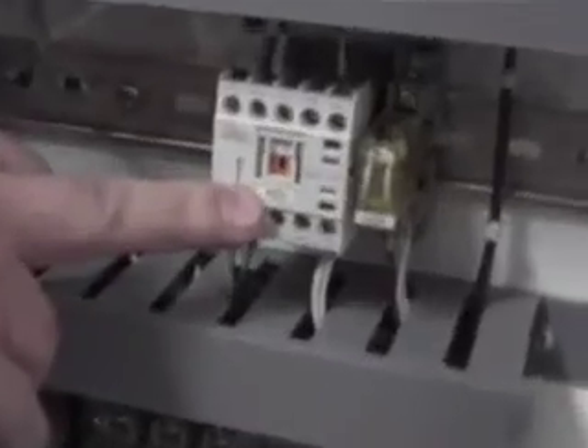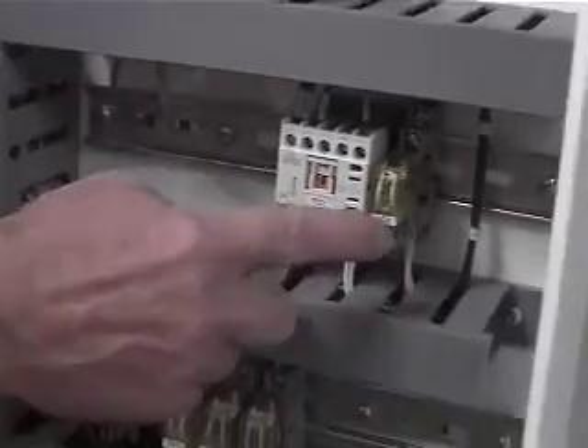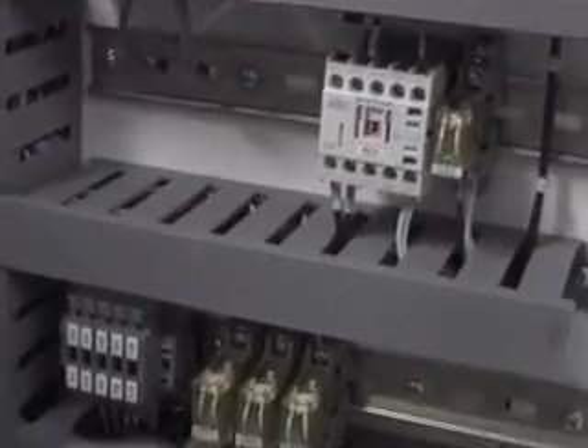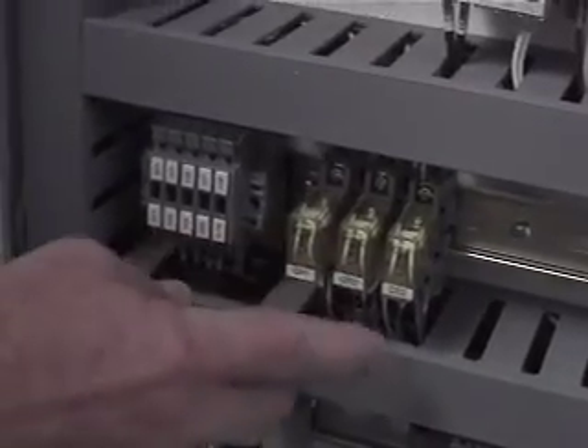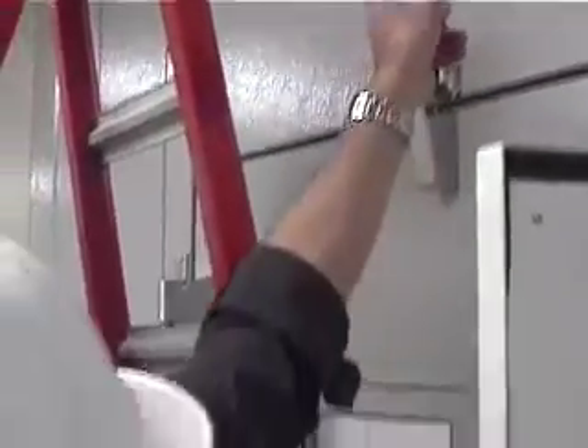Finishing our thoughts here. FC1, that's your fan contactor. LC1's your lighting contactor. We discussed these 2 here as your alarm contactors. CR3 is what energizes this one up here, so it literally is normally energized along with the personal emergency alarm. That's the way things are done in industry: the personal emergency alarm is energized if it's operational, and as soon as you de-energize it, everything goes crazy. It's low voltage, by the way. It's 24 VDC.